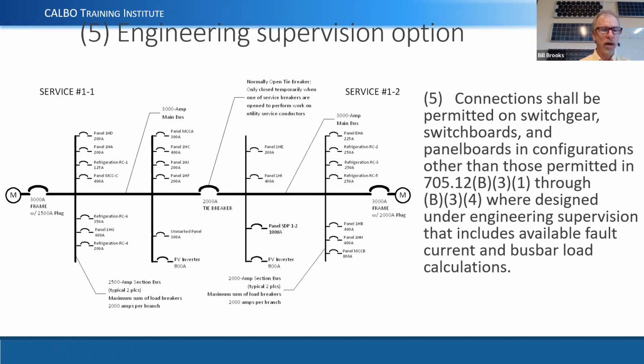All we're doing is making sure in this particular, this is an example of a project I was personally involved in. There was a 3,000 amp main bus with 2,000 amp branches coming off of it. And all we had to do is show that there was no way that we would ever get more than 2,000 amps on any one branch, and no way that in any possible configuration of loads and sources that we could ever see more than 3,000 amps on the main bus. That was a very easy solution. The calculations took about maybe an hour, maybe a half an hour, and it saved a ton of money and made the installation much cleaner. So like to see more people using that option as well.